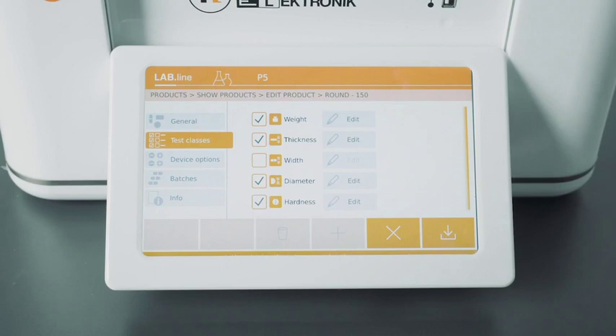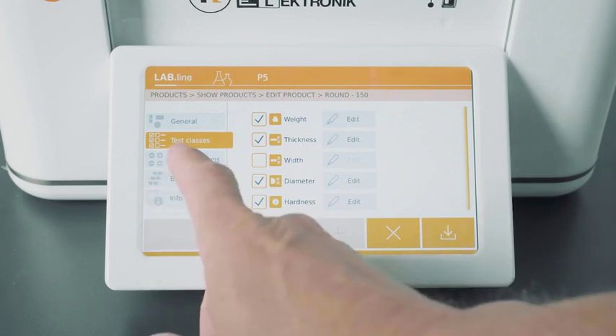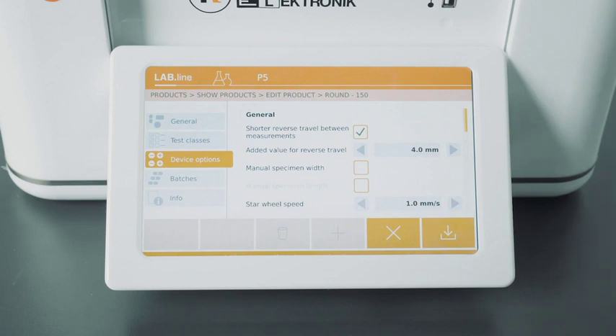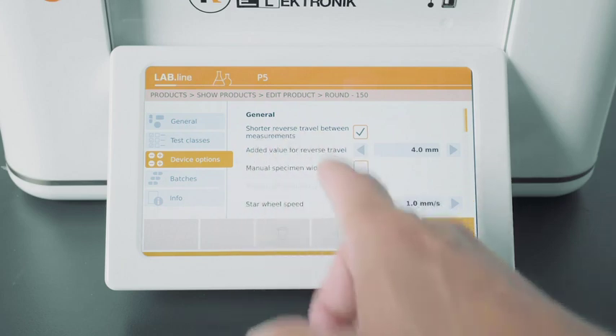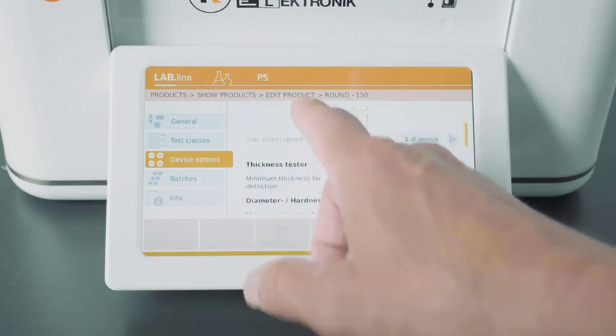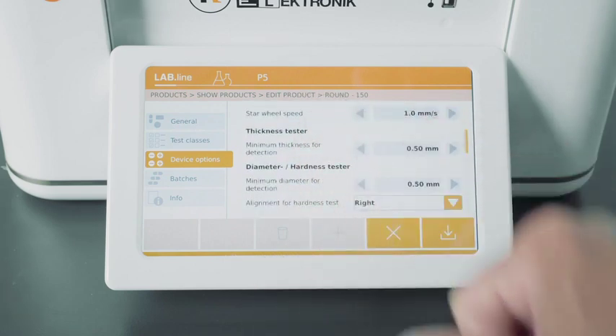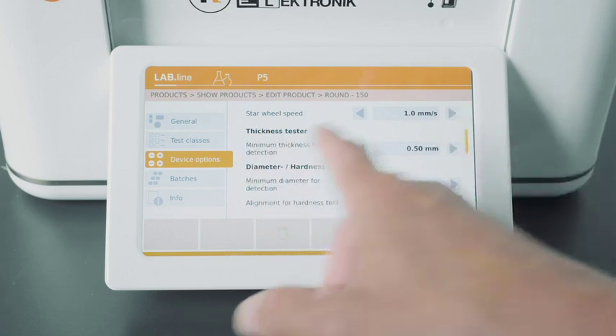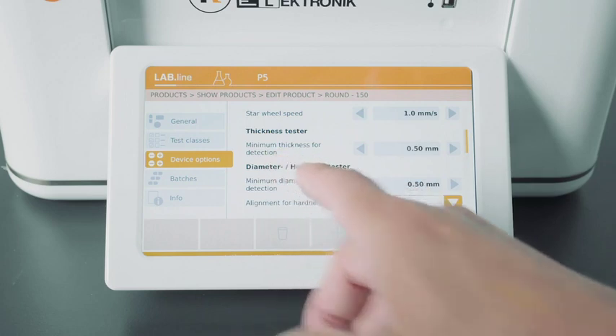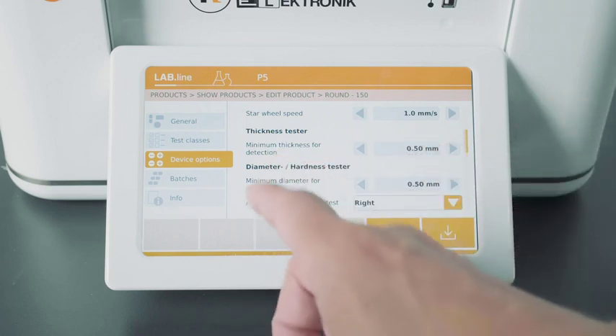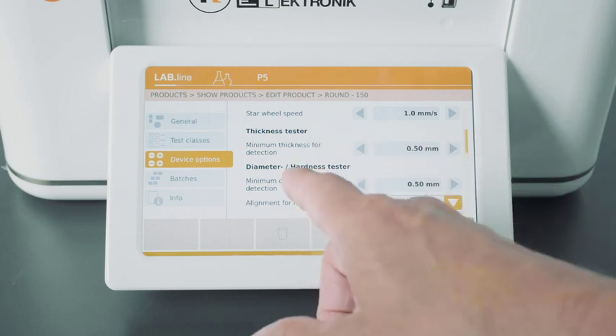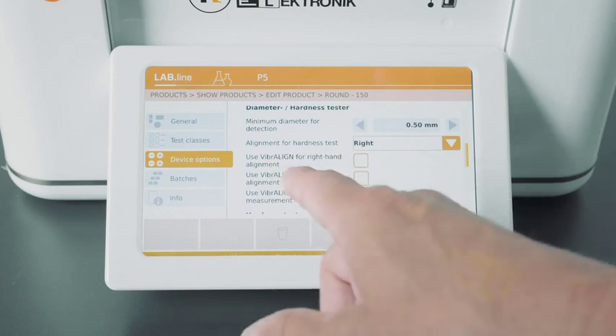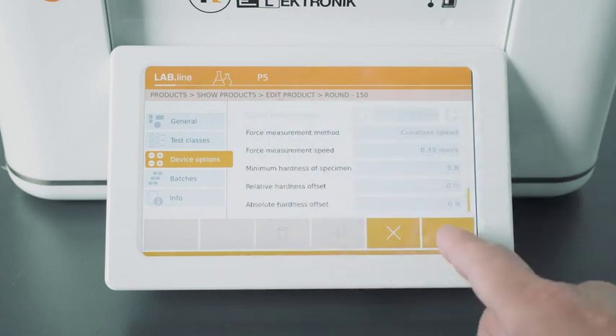So we have entered all the nominal values and tolerances, and we now move on to device options. The device options allow you to set up a number of parameters to better handle and orientate the product. Now we are entering a round tablet, so this is not critical for alignment. That means we don't need to set up anything here. There is star wheel speed, which you can leave at 1 millimeter per second as a standard. Thickness tester, minimum value for detection, 0.5 millimeter, that's usually okay. That means any values below are not being measured. The same for the diameter, and all the rest you can actually leave as it is and store.